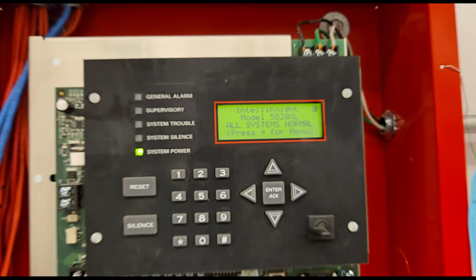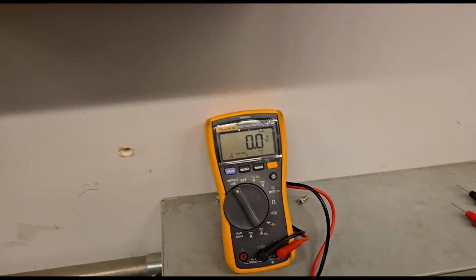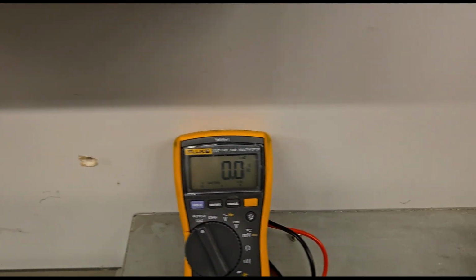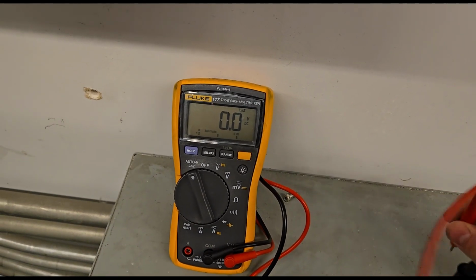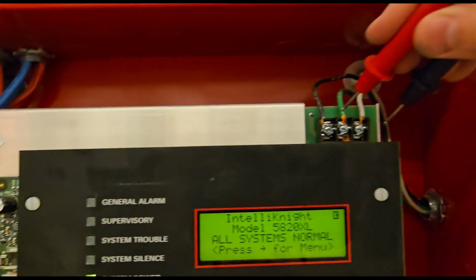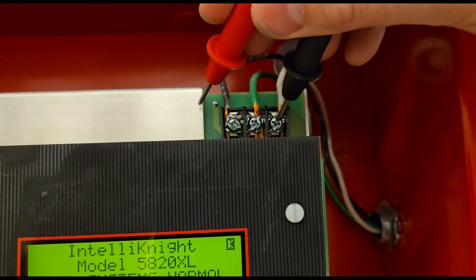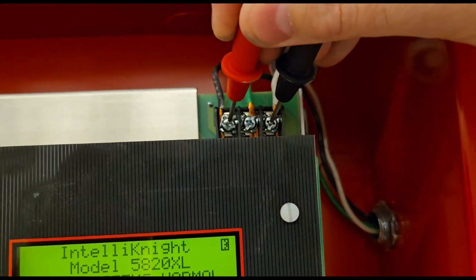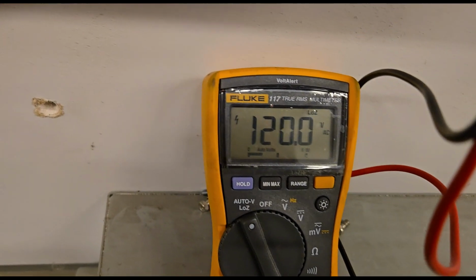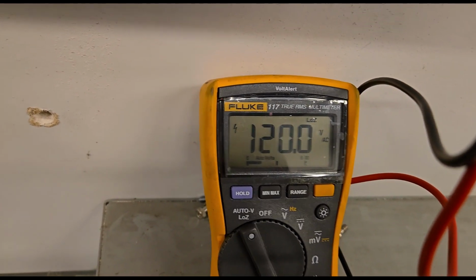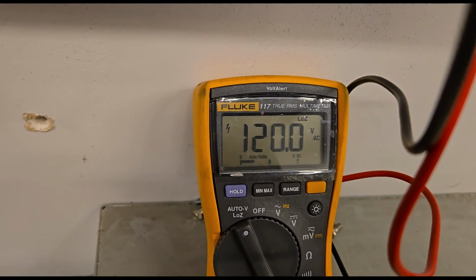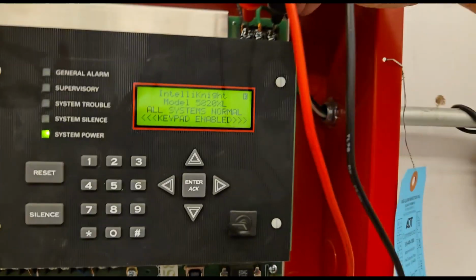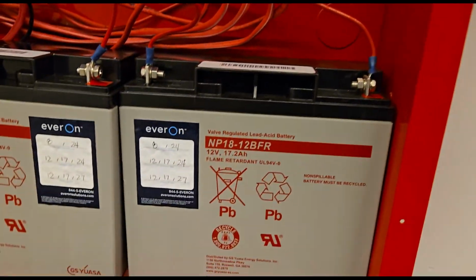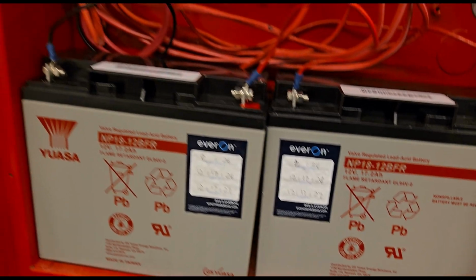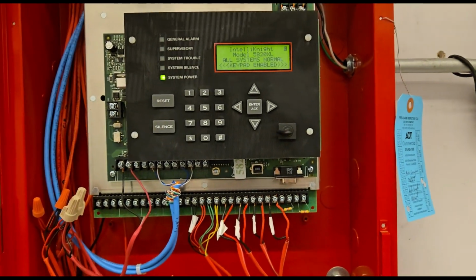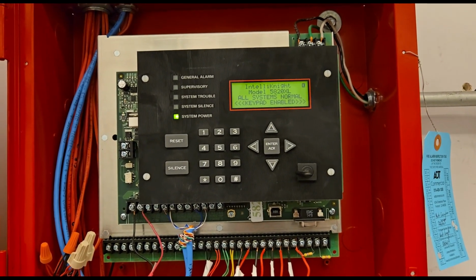All systems normal. And just one final time, already got my meter on. Gonna put our leads in, and there we go. 120 or 119.9. Kind of fluctuating back and forth. So our AC power is back on. And that is how we complete our circuit breaker test or our disconnect test of our fire panel.